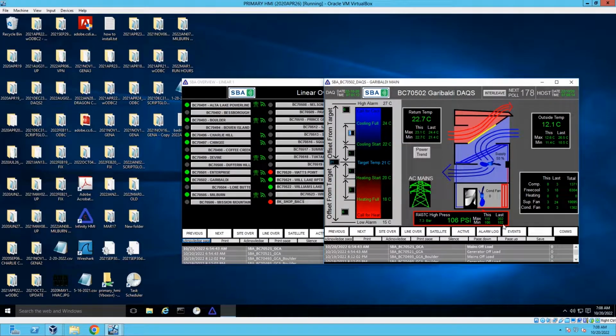We are also recording our compressor run hours, free cooling hours, heating hours, supply fan and condenser fan run hours for today, yesterday, and overall total. This allows us to compare min and max values and to plan service intervals based on actual run times. This graphic is exceptional at providing a reduction in maintenance costs by allowing our HVAC technicians to monitor site efficiency and deploy service personnel accordingly.